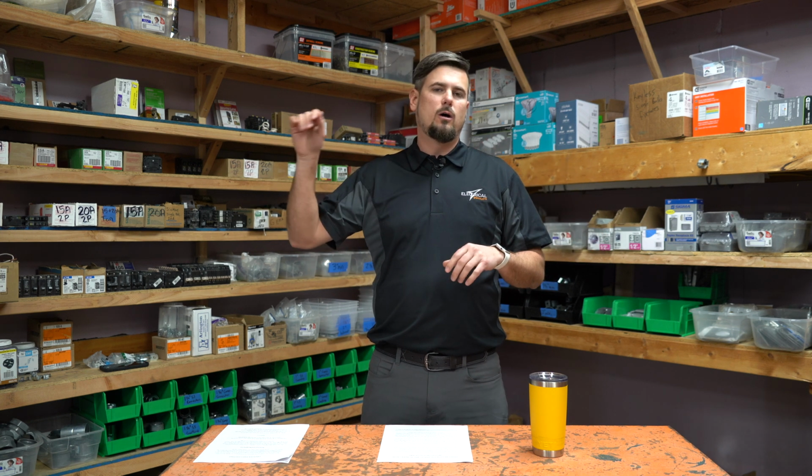Let's throw out a good list of some things to look for when you're walking around wanting to test stuff before they get there. You can walk around and test your fans for functions. You can pull the chains, check the remotes, make sure they all work. Look for bent or warped blades due to moisture. Those are going to make the list. If they wobble on low or medium, that's going to make the list. We all know there's a little wobble on high, but we typically don't expect it on low or medium. So if there is, you're probably going to have to replace that fan.